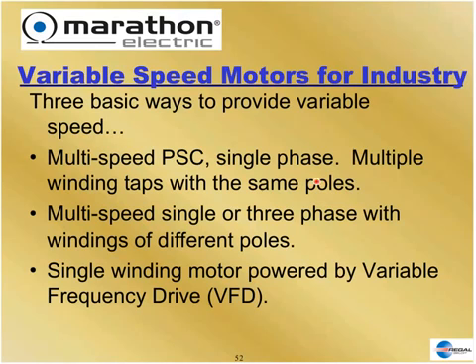We can also change the number of poles — putting in a four-pole and eight-pole motor gives two speeds. But if the customer wants any speed, there's only one thing left: frequency. Using a variable frequency drive gives any speed. But can change the number of poles for specific speeds, or use multi-speed taps for a few distinct speeds. For truly variable speed, the VFD is the solution.